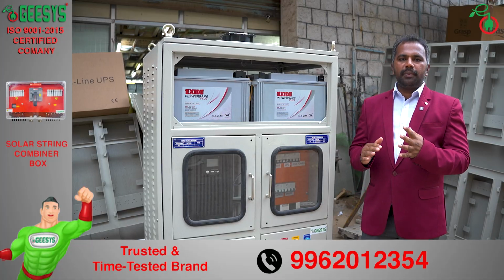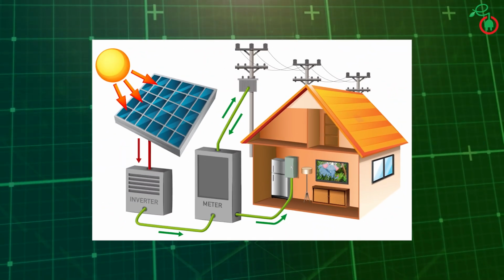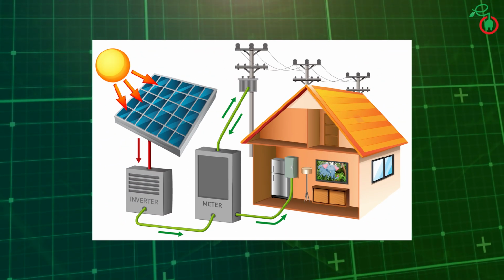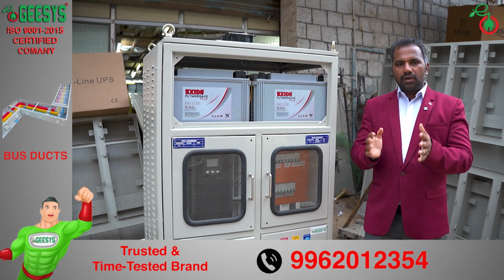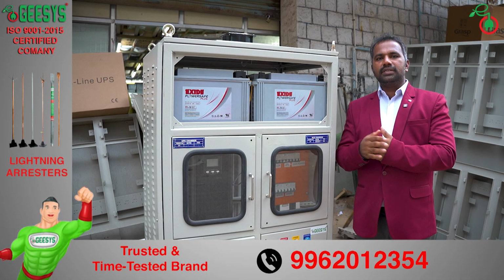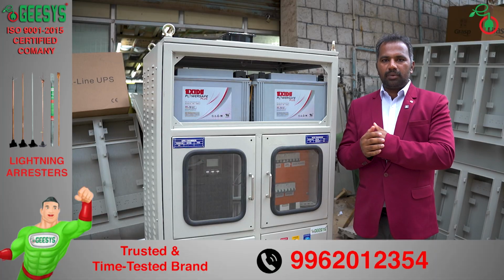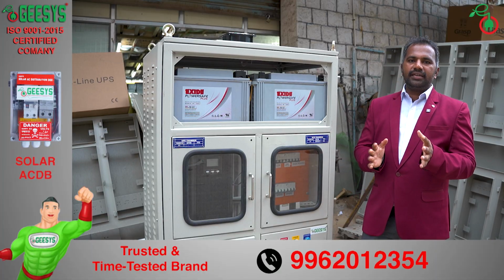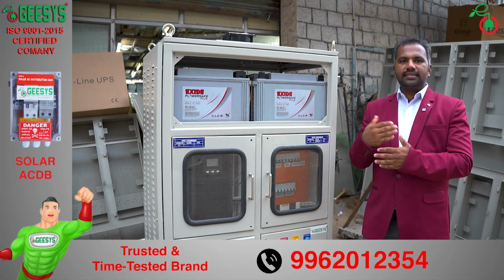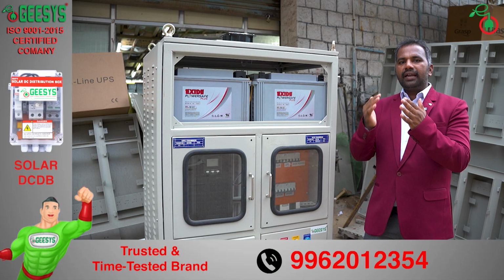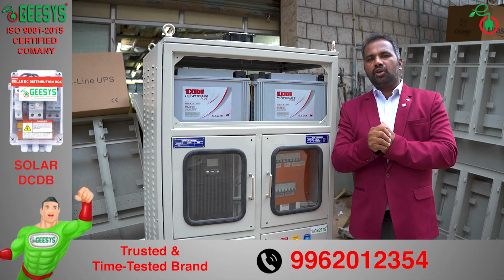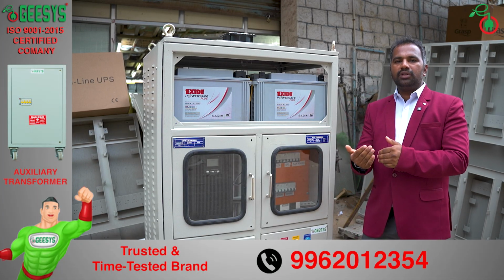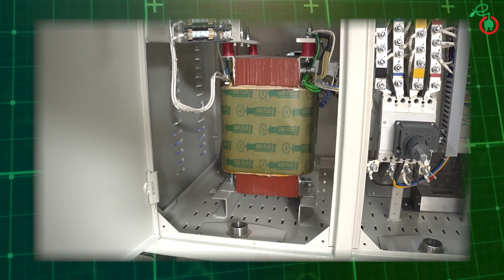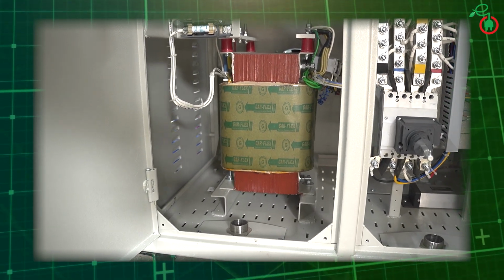Normally, the solar power plant generates power and sends it to the factories to use, or it sends it to the grid to sell. So the solar plant generates a voltage which is not used by the solar plant itself. Whatever the solar plant generates will be like a 660 or 690 or 800 volt system. That cannot be directly used for the solar plant equipment. So for that we have to step down the voltage from 660 to 450. That is done with an auxiliary transformer.